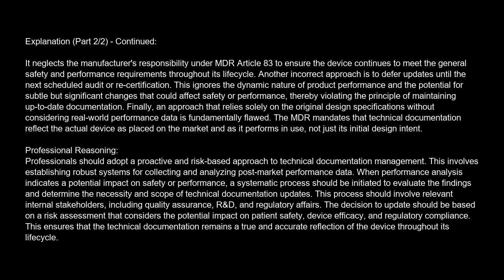Another incorrect approach is to defer updates until the next scheduled audit or recertification. This ignores the dynamic nature of product performance and the potential for subtle but significant changes that could affect safety or performance, thereby violating the principle of maintaining up-to-date documentation. Finally, an approach that relies solely on the original design specifications without considering real-world performance data is fundamentally flawed. The MDR mandates that technical documentation reflect the actual device as placed on the market and as it performs in use, not just its initial design intent.